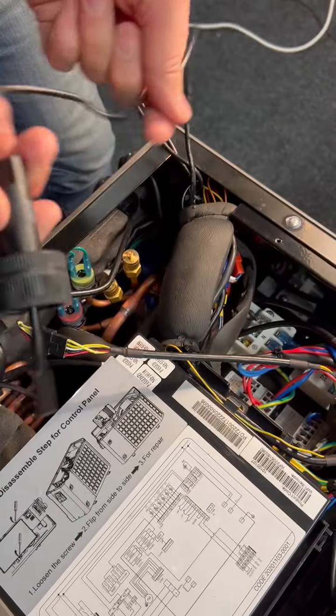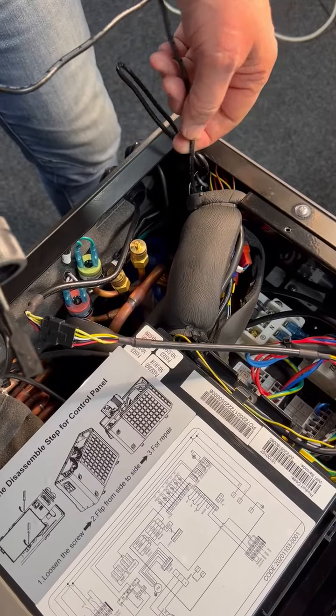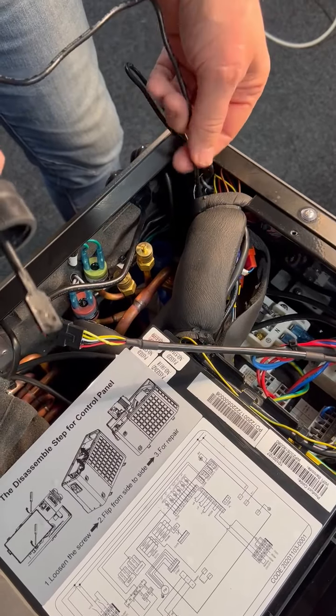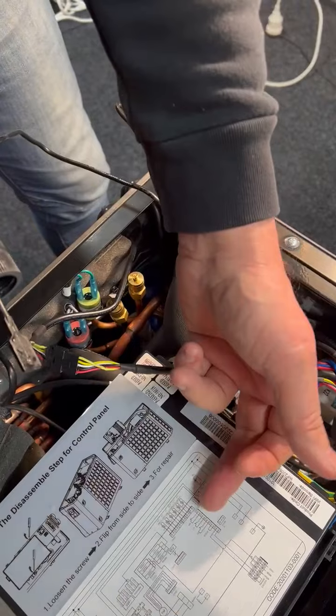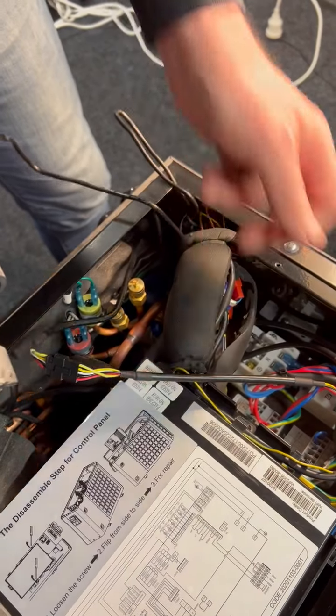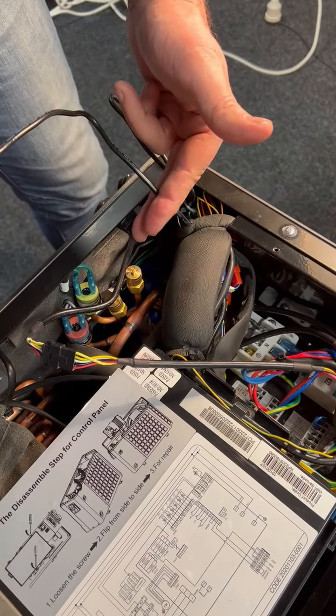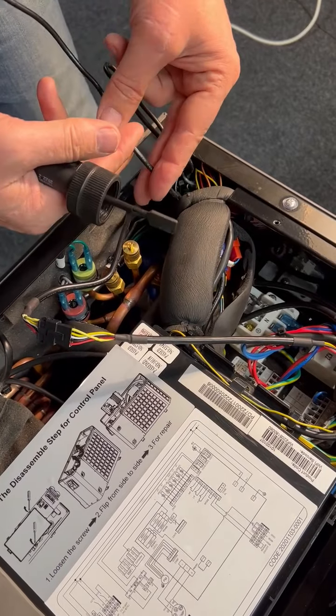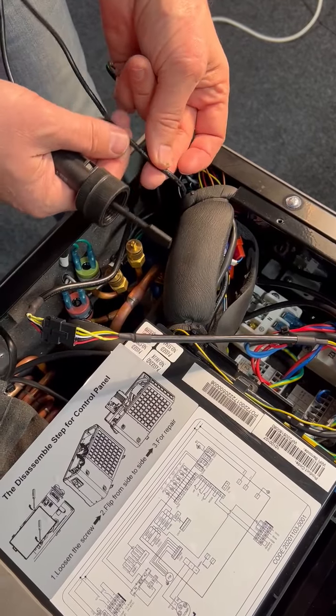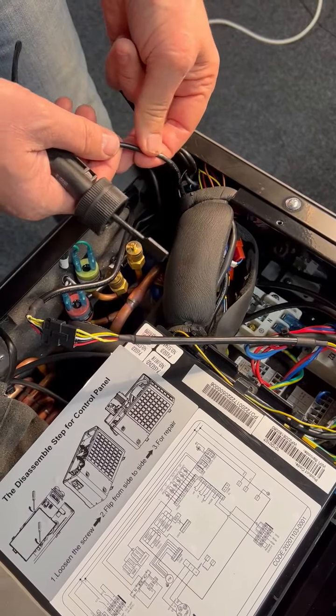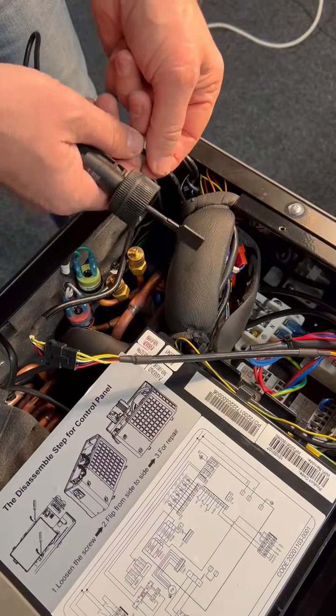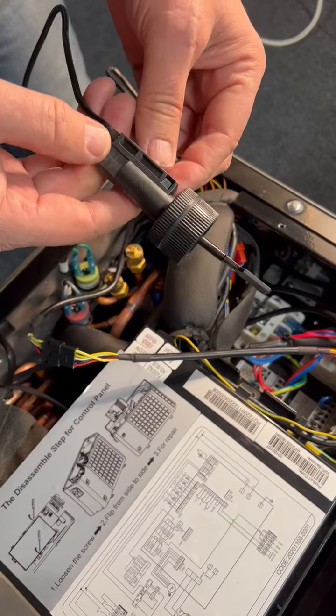Now that wire goes back to the microprocessor. It is sometimes easier, rather than pulling all the wire out and finding the connector inside the microprocessor, to just cut the wire here and you obviously splice it and put a joiner on and make that nice and secure, and then you don't have to worry about going into this area here. So once you've done that joiner there, all you do is put the flow switch back in.